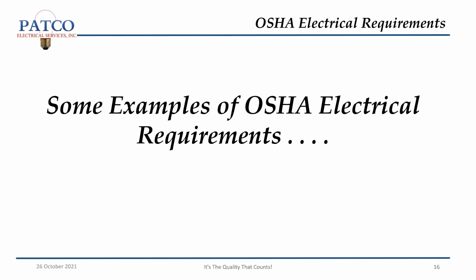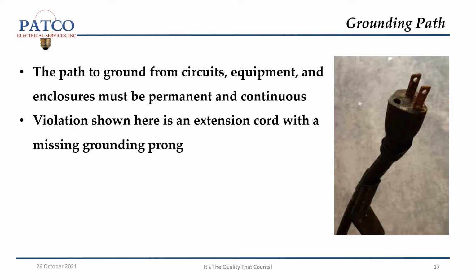OSHA electrical requirements. The next few slides are going to be some examples of OSHA electrical requirements. Grounding path. The path to ground from circuits, equipment, and enclosures must be permanent and continuous. The violation shown here is an extension cord with a missing ground prong. That's why it's important when you do your AGCP to make sure there is a grounding plug on all the extension cords and that they ohm out properly.